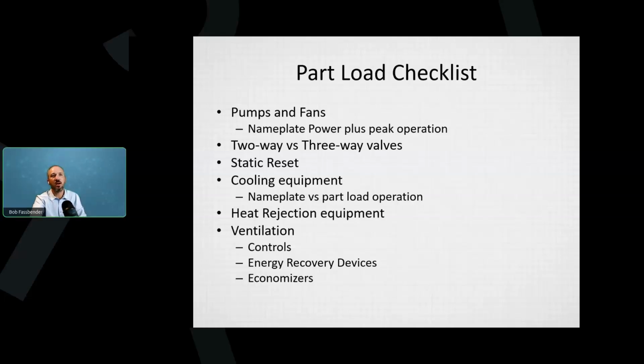There's another slide here. For pumps and fans, you want nameplate power plus the actual operation, if you can. A huge one here is to document whether there are 2-way valves or 3-way valves on any piping, because that's going to tell you how the pump unloads.